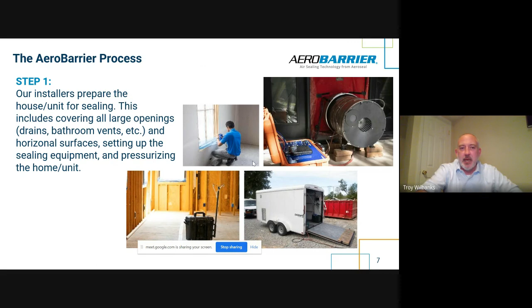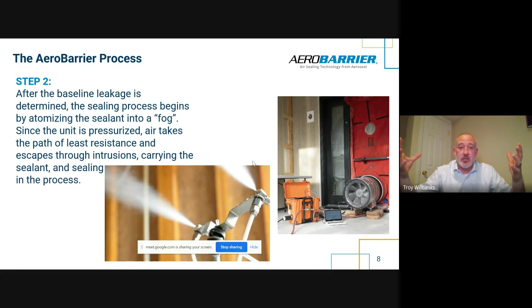Once it's pressurized, we do essentially a blower door test. So we get currently how tight or how leaky that space is. That's our baseline. And we have a predefined goal, whether it's code, whether we're looking for Passive House with 0.6, whatever it is. Once we do the baseline test, we know where we're at and where we need to go, which is perfect. So at that point, we start to atomize the sealant into essentially a fog, and then physics takes over. Positive pressure is going into the space, and air becomes our mode of transport. Air is traveling out of the unit through those leak points, and it carries our sealant with it and seals it up in real time.